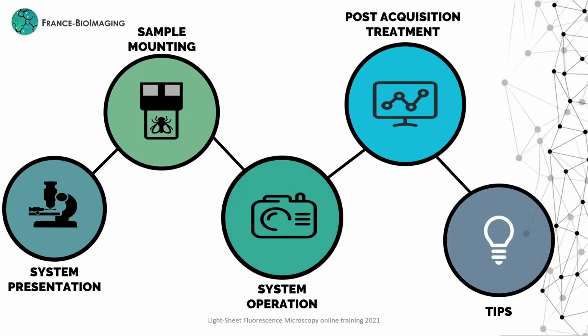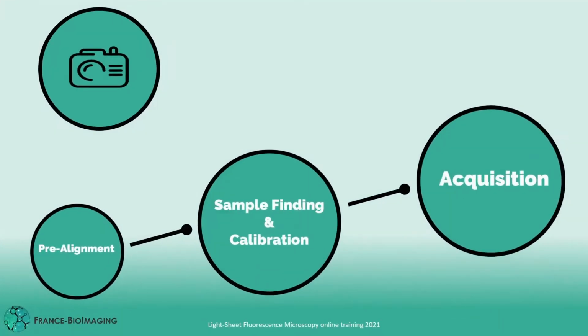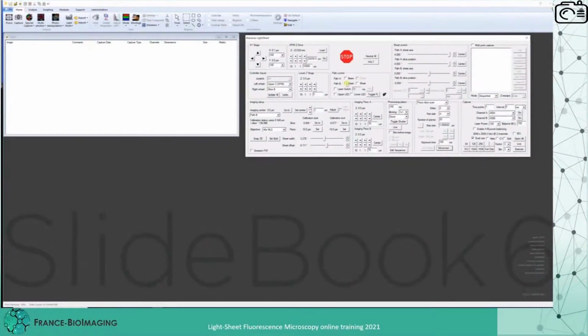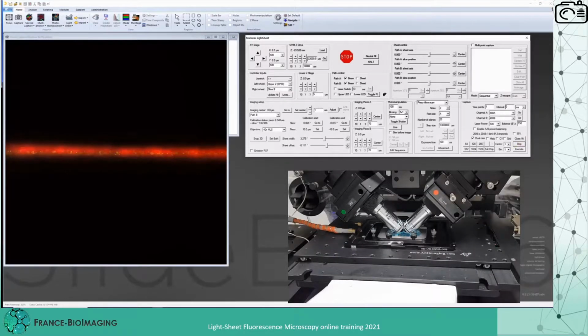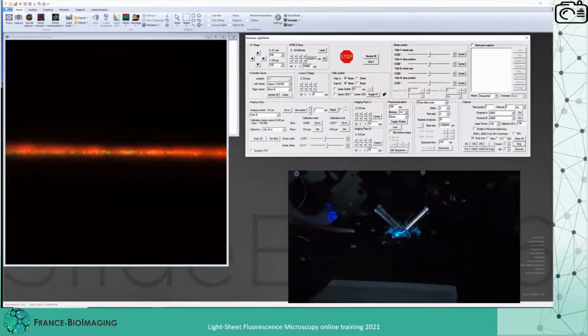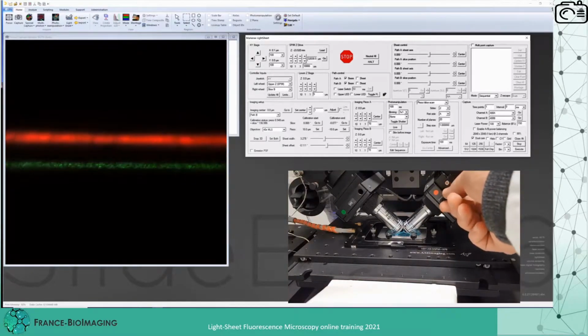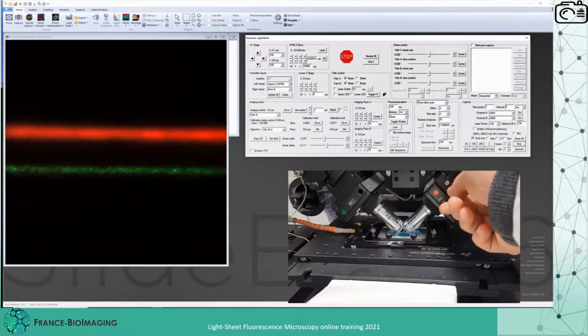Now that the system has been described and its mounting has been covered, we can move on to system operation, starting with pre-alignment. The system has been powered up and the chamber is currently filled with a fluorescent solution. The scanner is off so that we have a single beam on each side going through the sample. Both objective piezos are set to mid-range position and we are adjusting them so that both beams are in focus.